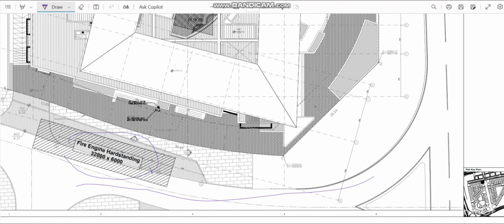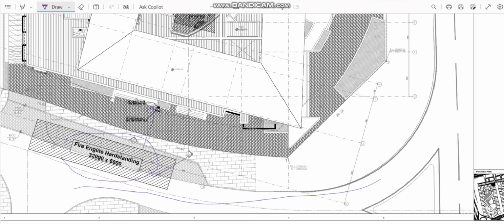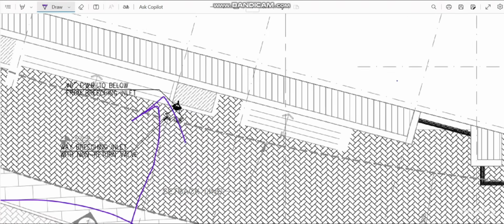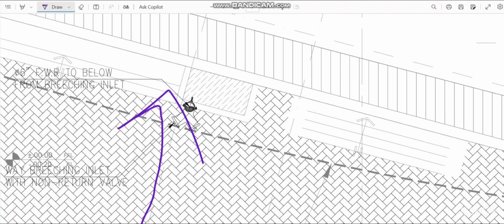Here they have made the arrangement for the fire engine hard standing, and this should be accessible within a particular distance. So at this level, we have provided the breeching inlet. You can see here we have provided the four-way breeching inlet at this point. This is the ground floor. We have the fire pump room in the first basement, so from here it will go down and connect with the fire pump room. I will show you that also.